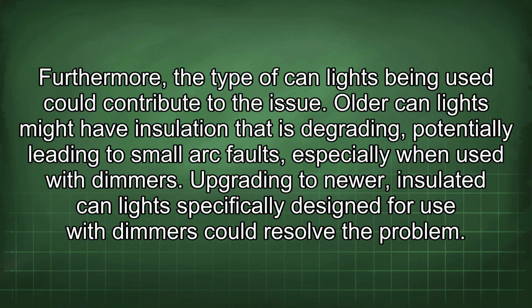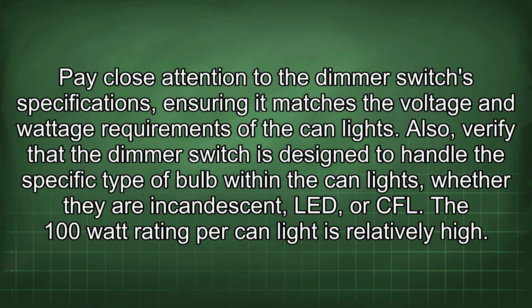Furthermore, the type of can lights being used could contribute to the issue. Older can lights might have insulation that is degrading, potentially leading to small arc faults, especially when used with dimmers. Upgrading to newer, insulated can lights specifically designed for use with dimmers could resolve the problem. Pay close attention to the dimmer switch's specifications, ensuring it matches the voltage and wattage requirements of the can lights. Also, verify that the dimmer switch is designed to handle the specific type of bulb within the can lights, whether they are incandescent, LED, or CFL.